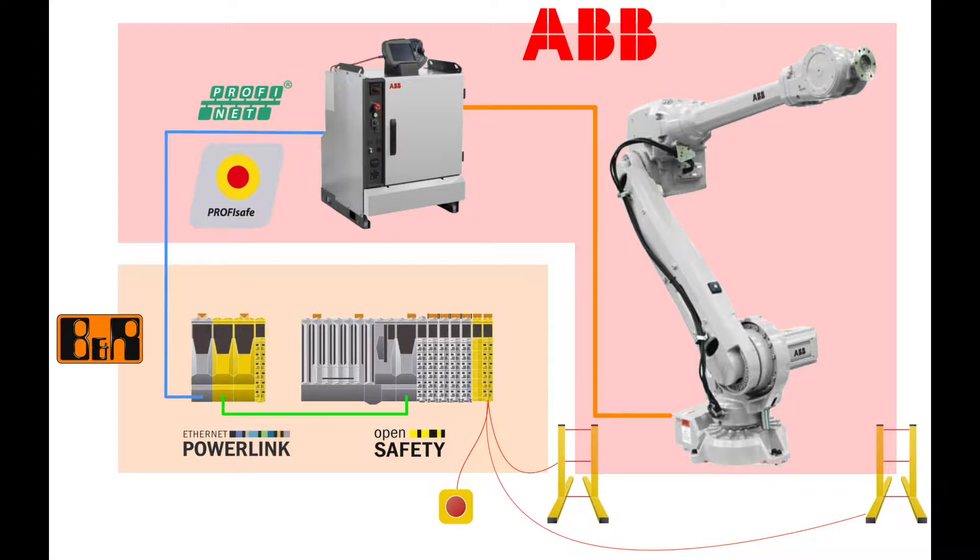Our physical setup includes an ABB IRB4600 robot controlled by an ABB IRC5 controller, which is talking ProfiNet to a B&R X20 PLC. That PLC has an integrated safety X20 PLC connected to it, which has three safe digital inputs connected to it: an e-stop and two area scanners. Now I'm going to show you how to set up ProfiSafe communication between the IRC5 and the B&R Safe PLC.